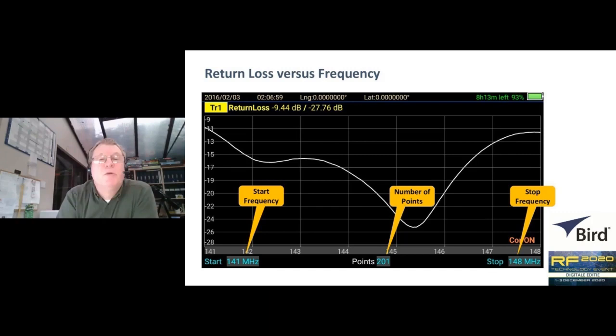At the bottom of the screen we have the words start and stop. By touching either word, we can define the range of frequencies being swept - in this example, 141 to 148 megahertz. By touching the word points, we can define the number of discrete frequencies between the start and stop frequencies - in this example, 201. The higher the number of points, the greater the accuracy and the smoother the graph, but also the slower the sweep time.